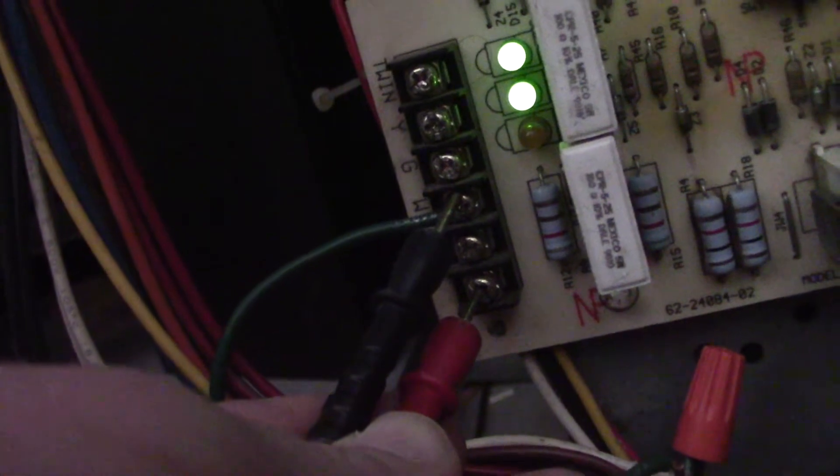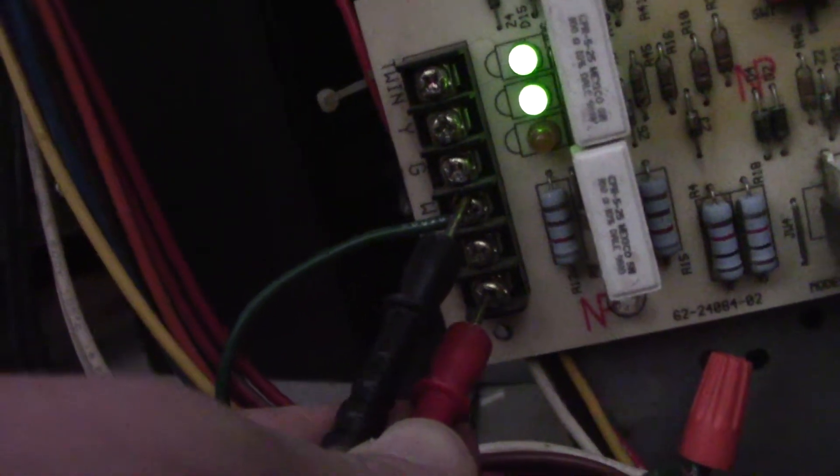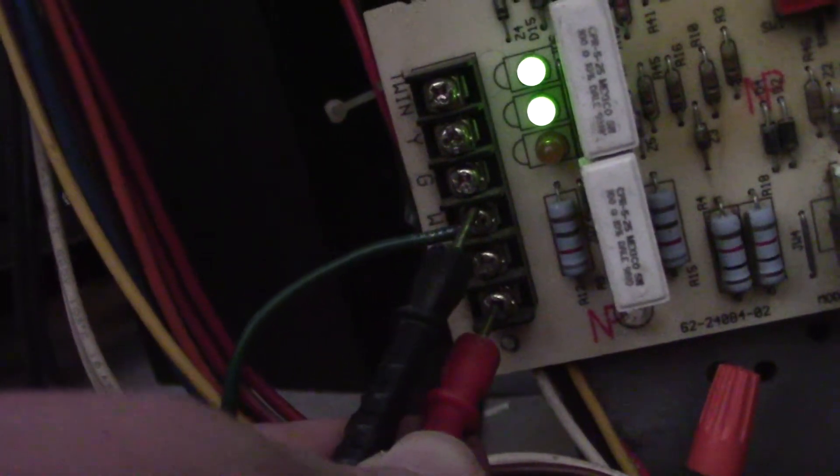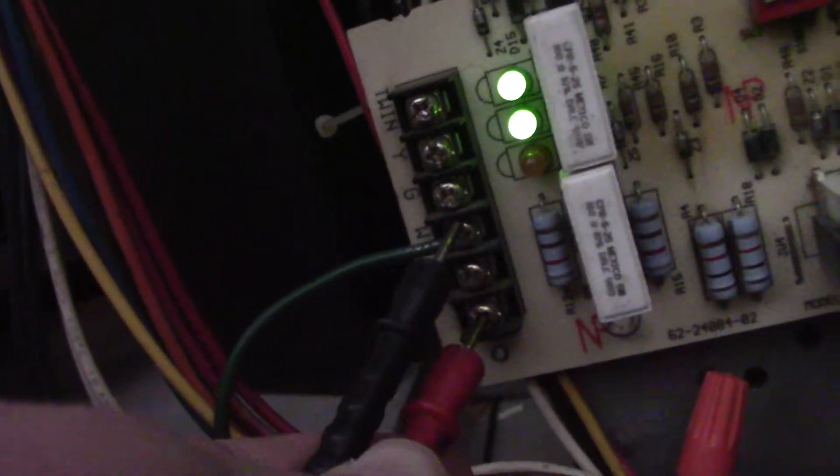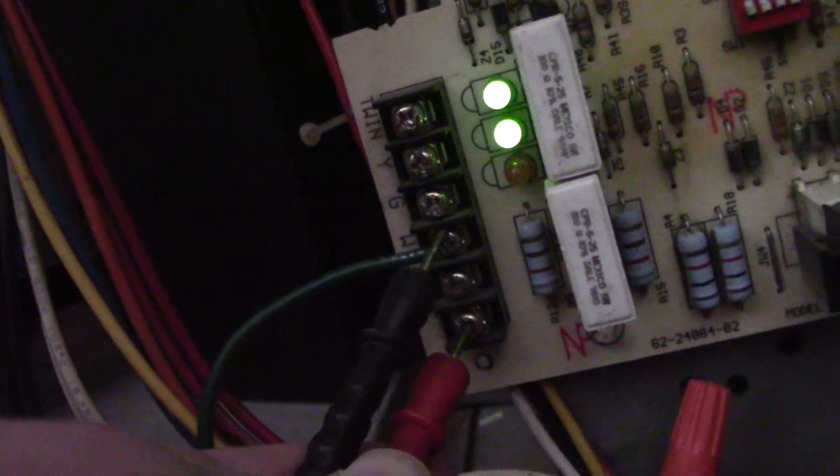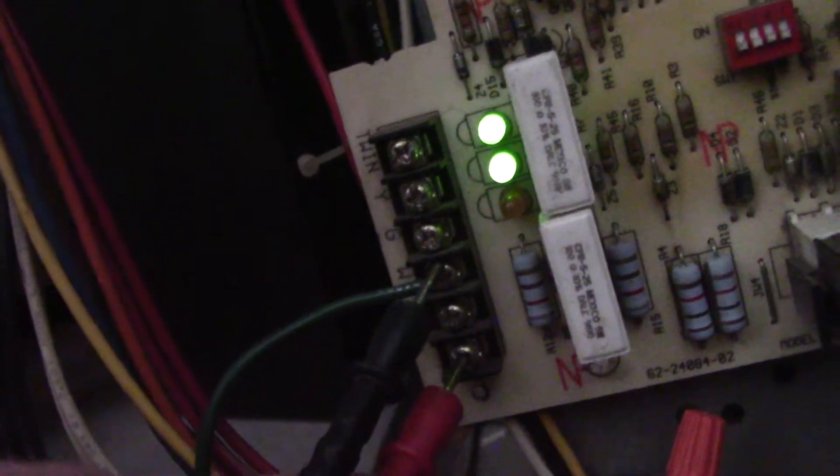If you've got 24 volts here, you know that the thermostat has sent power through. You may be looking at a bad board.